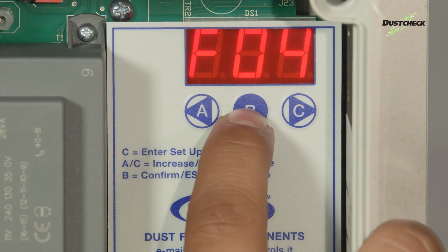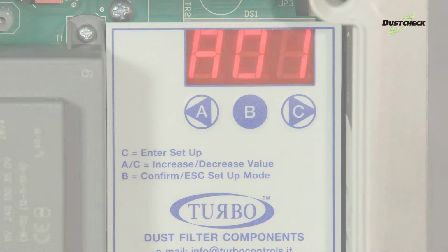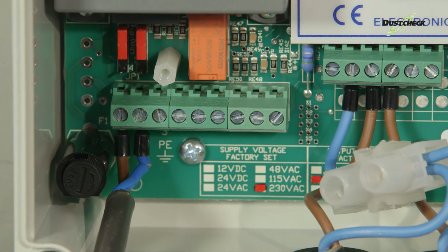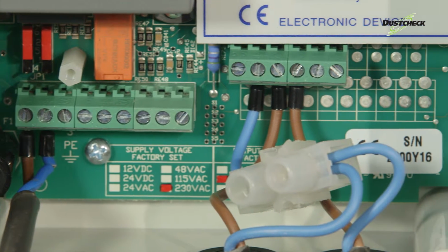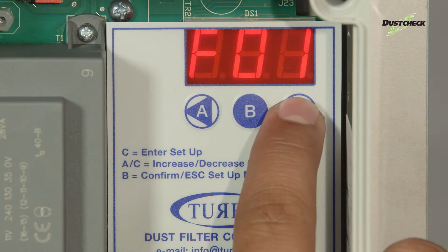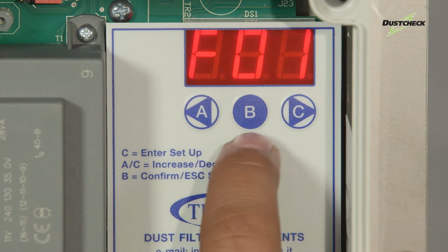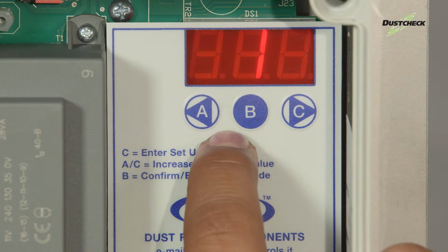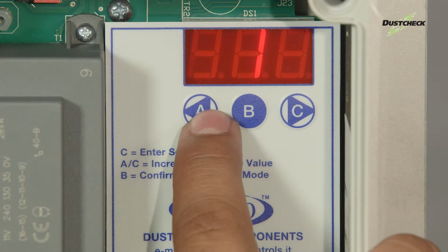Let's now go through each function and setting in turn. Since the controller requires a power supply during the setting operation, extreme care should be taken to avoid contact with live terminals. Function F01 is to allow the controller to stop and start via an external signal using terminals 12 and 13 or 14 and 15, or all 4. The normal factory setting is 1, which ignores any external signal. Setting to 0 allows this signal to be used.